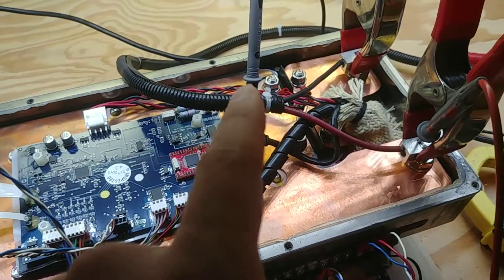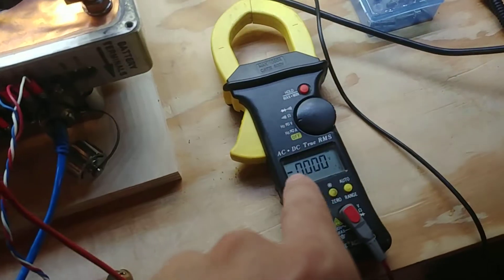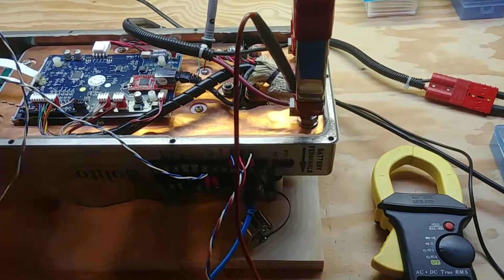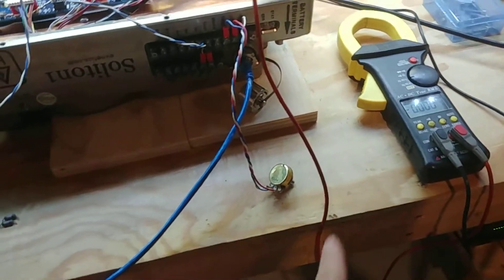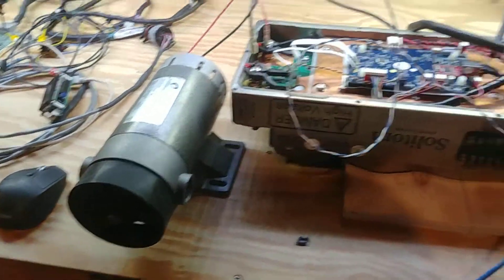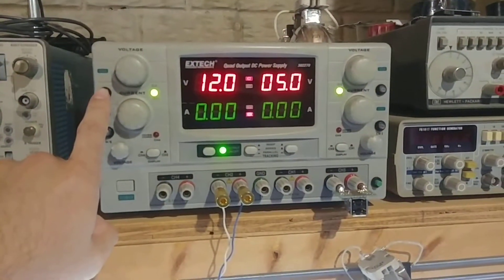So when we turn it on, the relay will click on. It'll pre-charge. We'll see this get up to about 170 volts and then the drive will power up and we'll be able to spin the motor. So I'll go ahead and show you that here by flipping on main power.